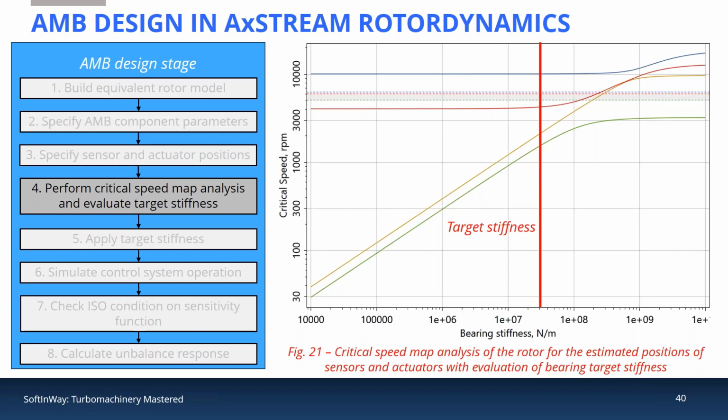So it can be applied to any rotor in general. Another question is the applicability of active magnetic bearings to a certain machine. It should be ensured by considering the ISO standard for this case. And the rotor dynamics analysis of the rotor and AMB system in AxSTREAM RotorDynamics is based on both ISO and API standards, which will answer this question.